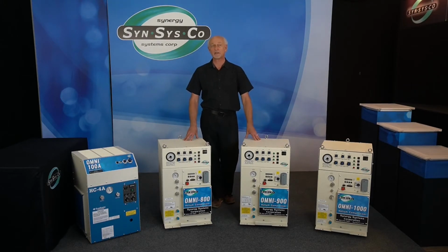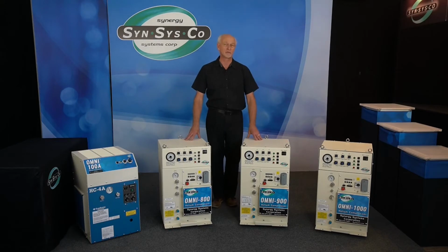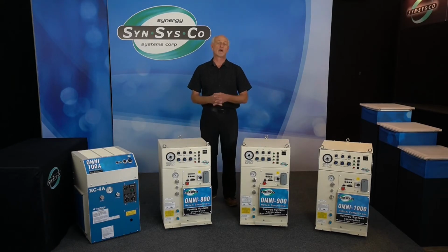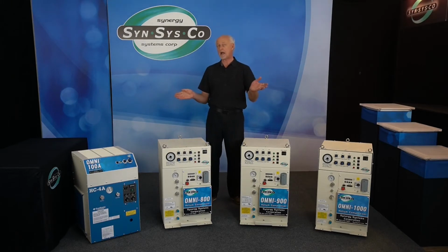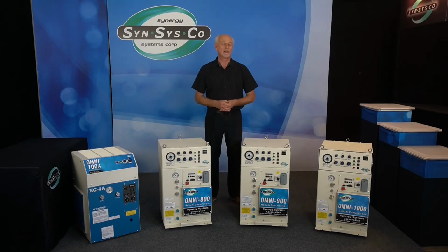Once you've installed the OMNI, it opens up other opportunities. Because it can drive cryopumps made by different manufacturers, it will run the ones you have, but you may find another cryopump has superior operating characteristics to the one already installed. This gives you the opportunity to remove the existing cryopump when it needs service and install a higher performance cryopump that could improve your capabilities. We'll get into that in more detail at the end of the video.